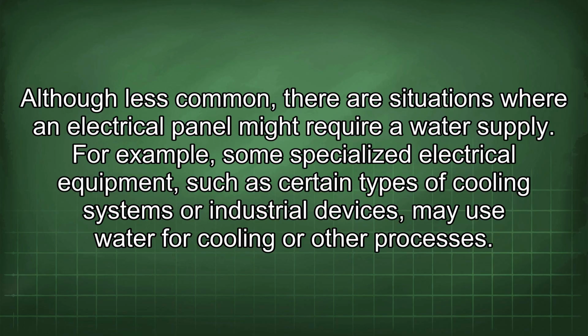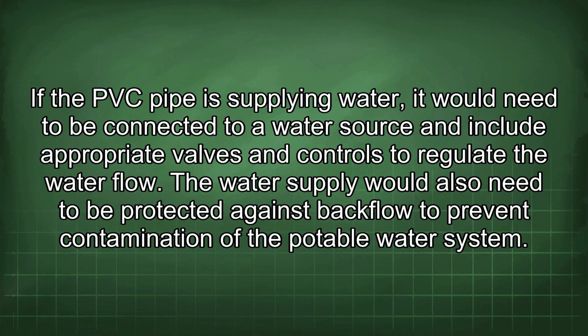Although less common, there are situations where an electrical panel might require a water supply. For example, some specialized electrical equipment, such as certain types of cooling systems or industrial devices, may use water for cooling or other processes. If the PVC pipe is supplying water, it would need to be connected to a water source and include appropriate valves and controls to regulate the water flow. The water supply would also need to be protected against backflow to prevent contamination of the potable water system.